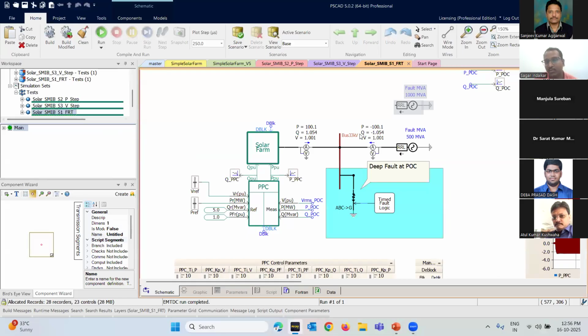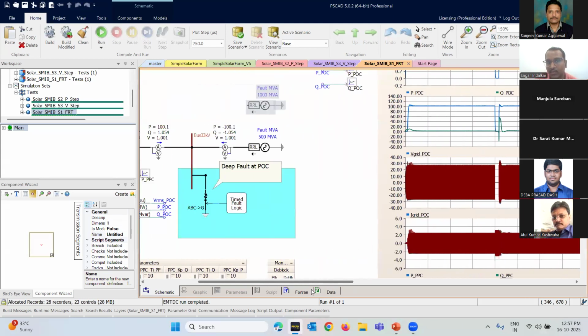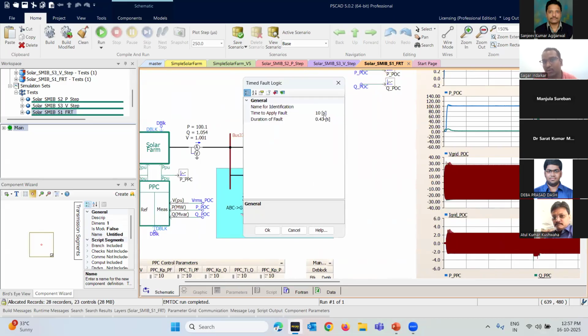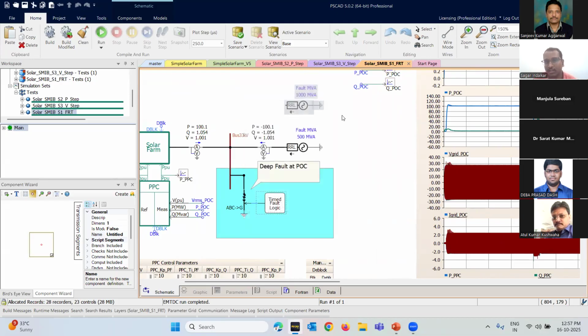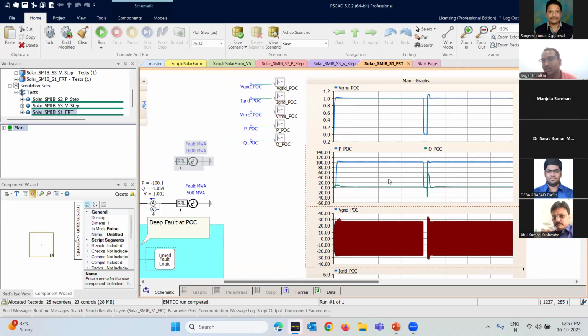At the end, what you have to perform is the fault ride-through. We will apply a deep fault at the PCC. Typically, these are performed at 85% voltage, 50% voltage, and 15% voltage, and then you specify the duration of that fault, for example 0.43 seconds. What we have to check is whether the plant remains connected to the grid even during this LVRT event, and whether it comes back to normal and stable after the event goes away.